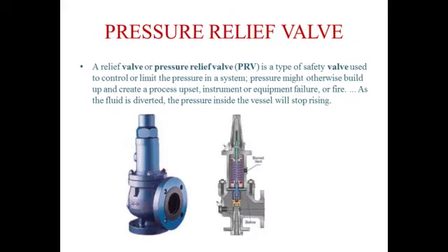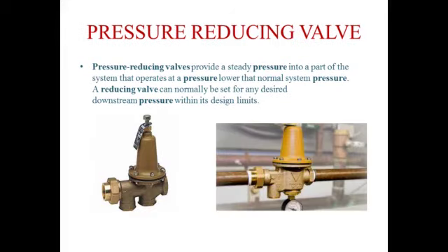Pressure relief valve. A relief valve or pressure relief valve is a type of safety valve used to control or limit the pressure in a system. Pressure might otherwise build up and create a process upset, instrument or equipment failure, or fire. As the fluid is diverted, the pressure inside the vessel will stop rising. This is mainly used in hydropneumatic systems to control the pressure. The pressure built in the pipes may lead to bursting of the pipes. So, in those places, the pressure relief valve is used to relieve the pressure in the pipes and maintain constant pressure in the system.